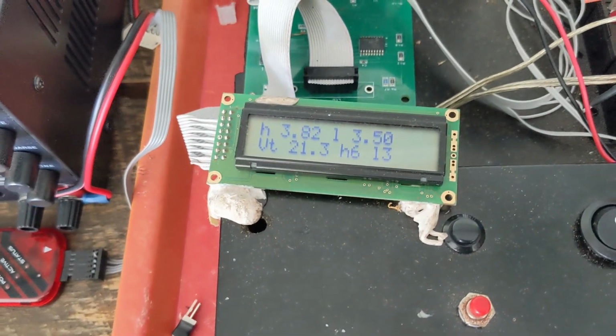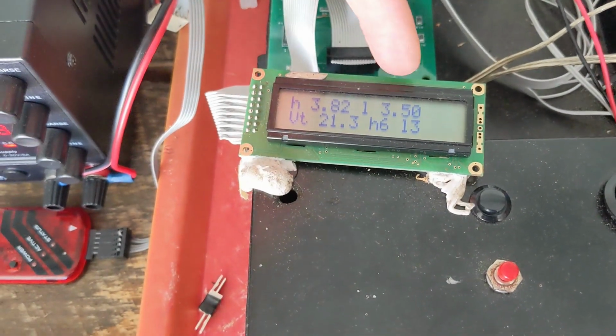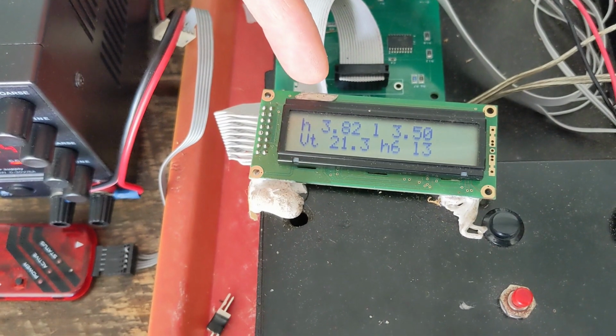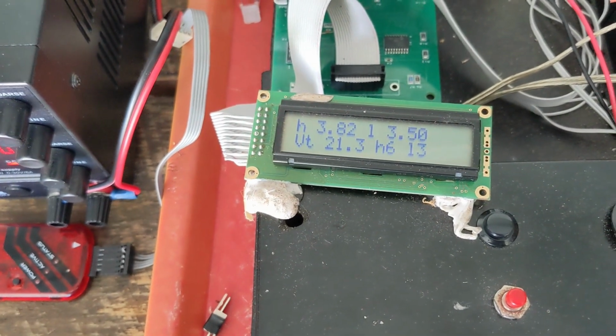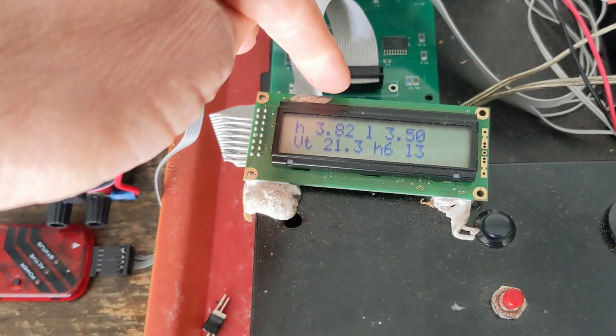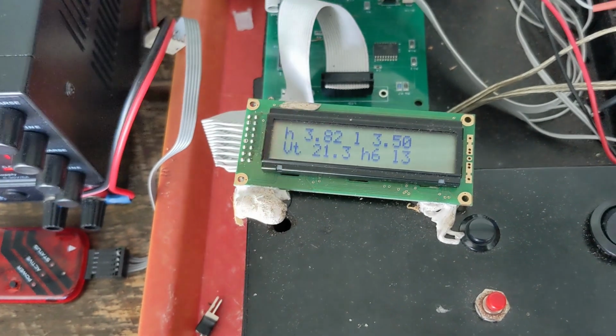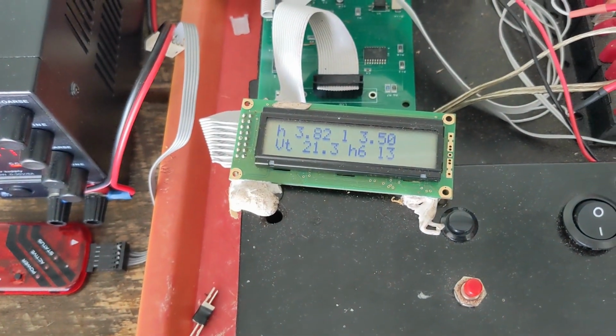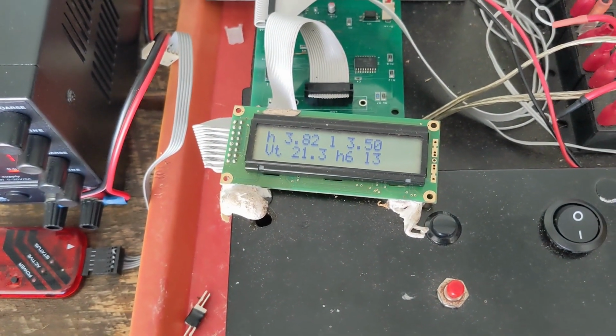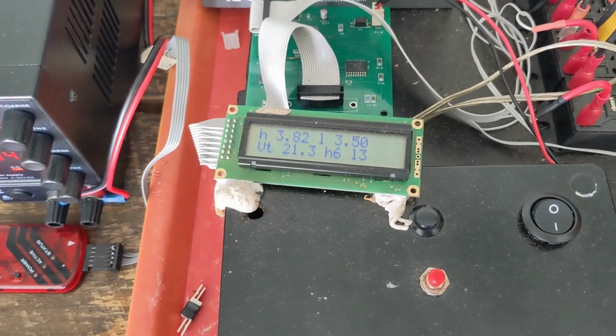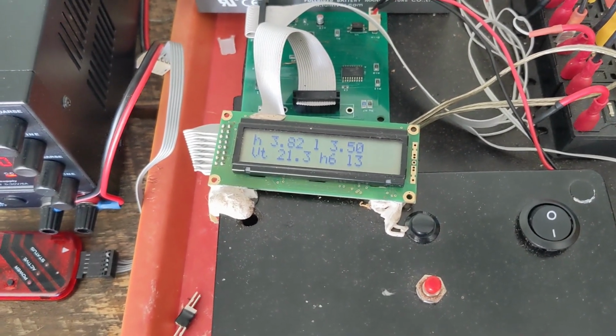Looking at the display on the master unit, you can see 3.50 is the lowest, 3.82 is the highest, which was what is shown on the display over there. I'll use this as a test. I'll take this one down to 3.1 and make sure that the relay opens and our load is disconnected.